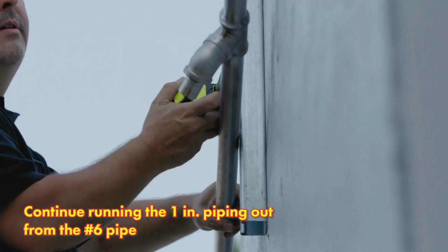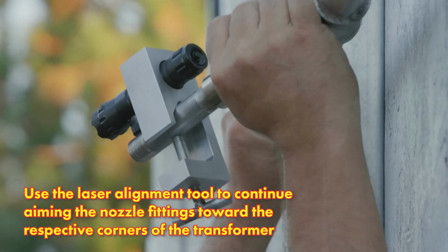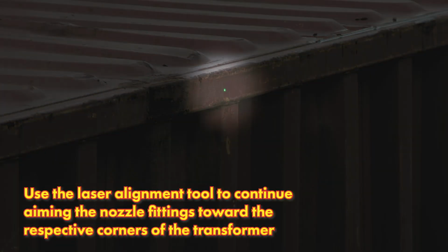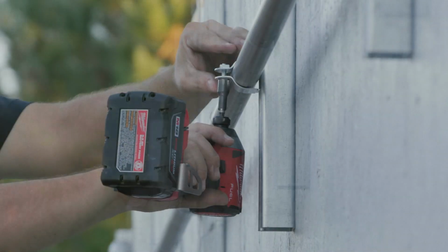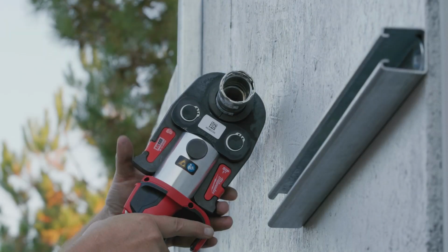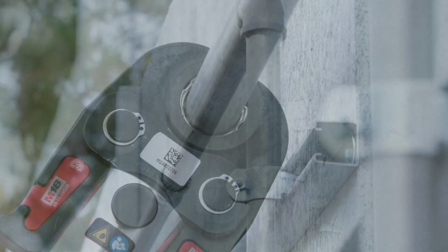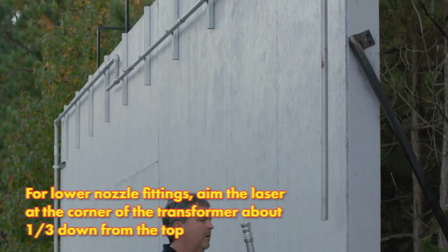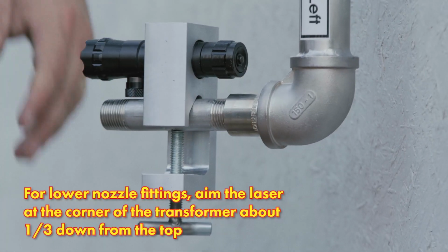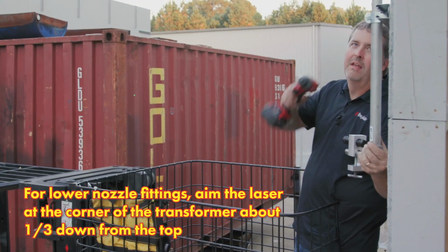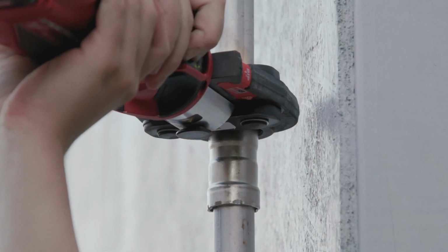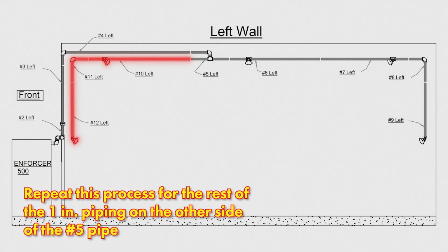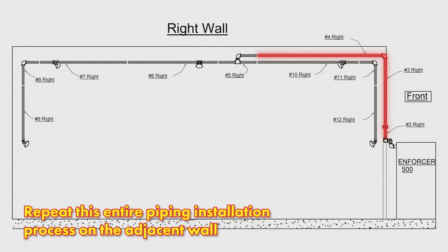Continue running the 1 inch piping out from the number 6 pipe, using the laser alignment tool to continue aiming the nozzle fittings to the respective top corners of the transformer. For the lower nozzle fittings, aim the laser at the corner of the transformer about 1/3 down from the top. Repeat this installation process for the section of 1 inch piping on the other side of the number 5 pipe, then repeat the entire piping installation for both the 1 1/2 inch and 1 inch piping segments on the adjacent wall.